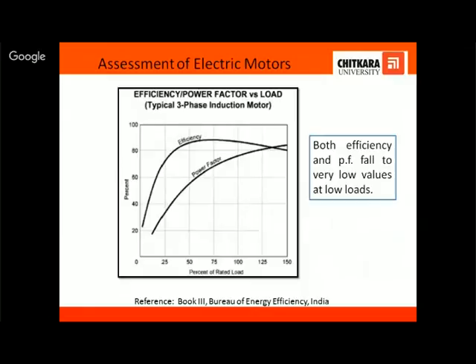So one needs to know the torque-speed characteristics of the motor, and how the power factor and efficiency of the motor vary with the load. Now we see that as the load drops, the efficiency also drops, and even the power factor drops. So the motor operates at a very low power factor at lesser loads. As the motor gets loaded, the power factor improves.